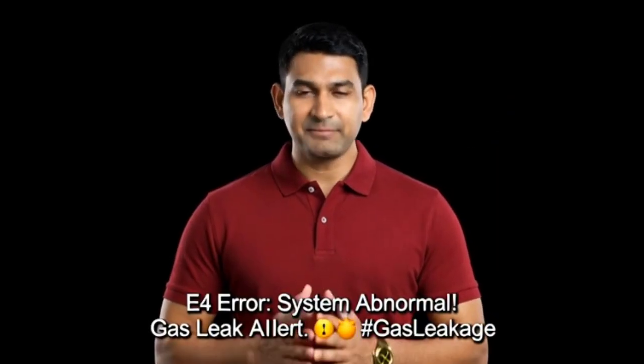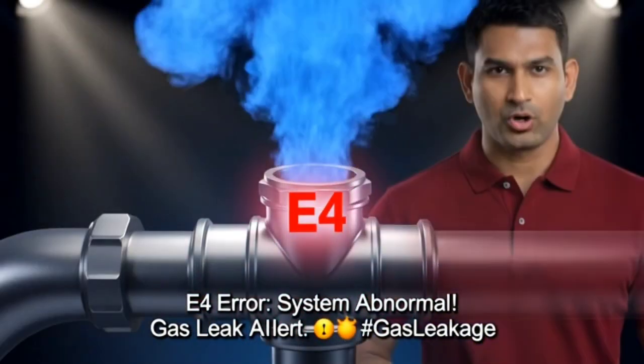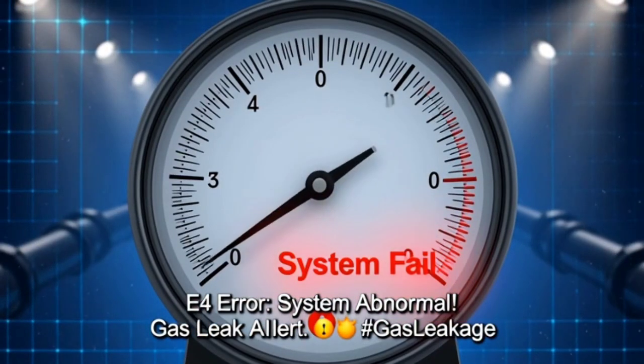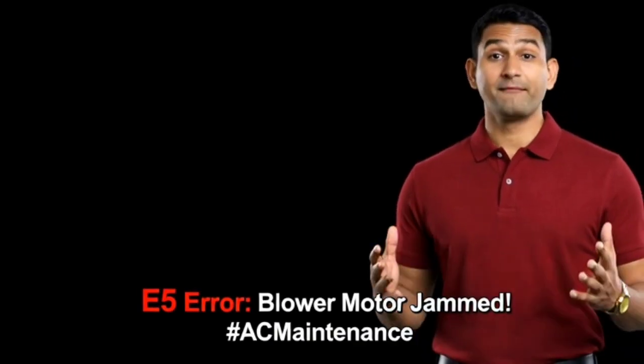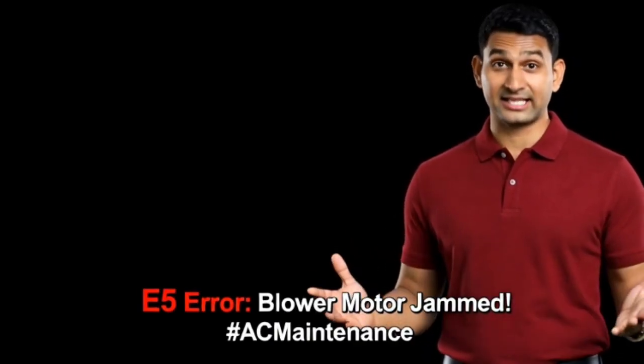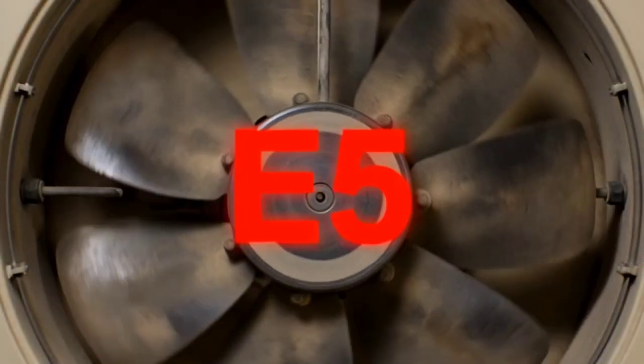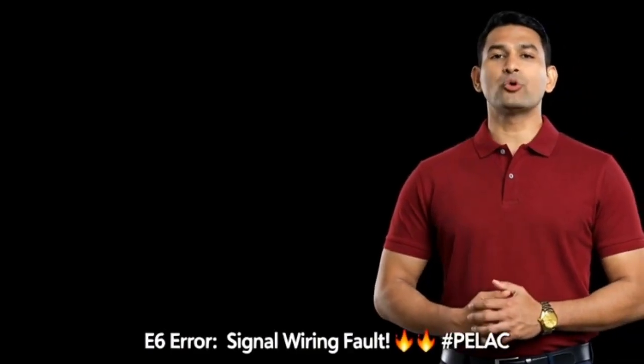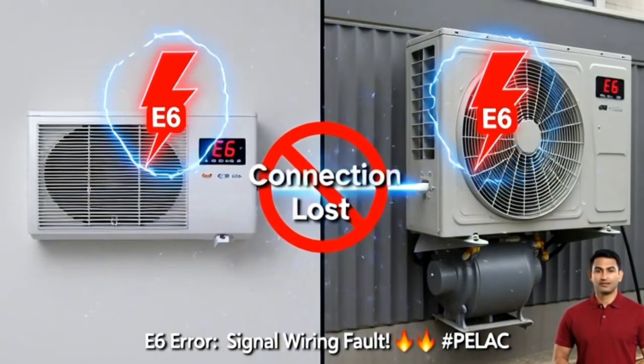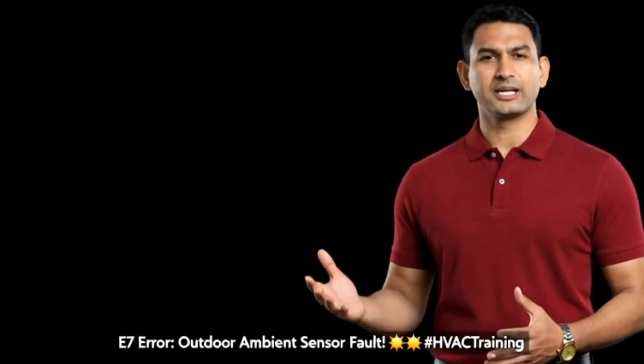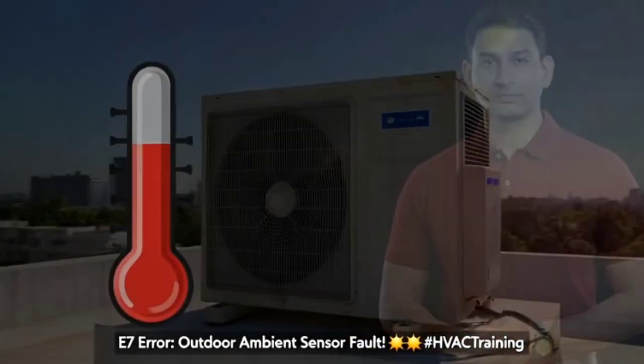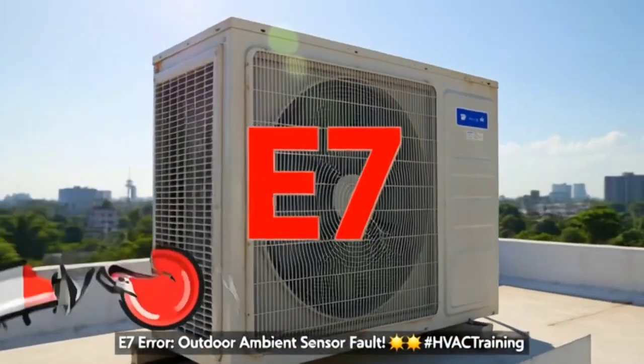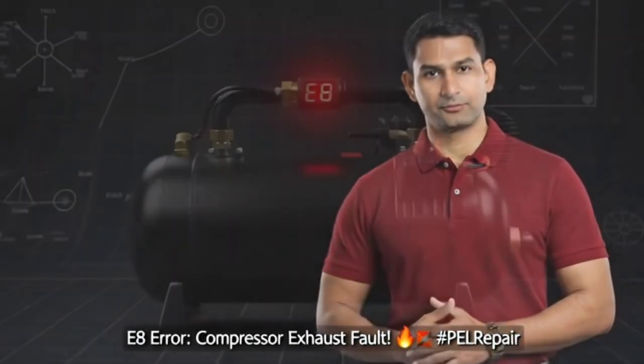E4 alert. This means gas leakage or a compressor pump failure. E5 means your indoor fan motor is jammed or the wire is cut. E6 is a communication error between the indoor and outdoor units. E7 means the outdoor weather temperature sensor is no longer working. E8 indicates a faulty exhaust sensor on your AC compressor.